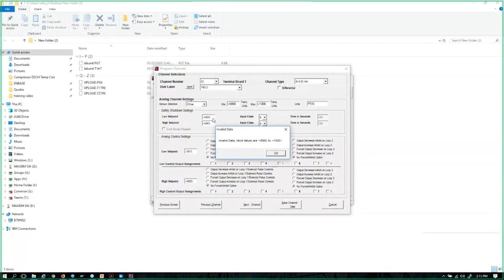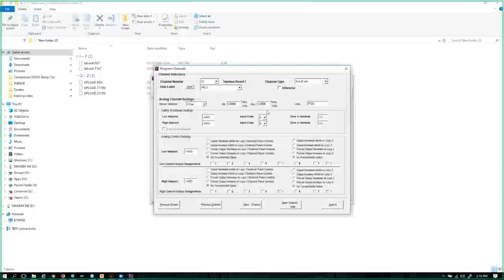And it's telling me my values are invalid. That's kind of a pesky little message, because usually you say okay twice and it'll change the values over here automatically for you. But now that you've selected the sensor type as other, you scale it manually. So we'll tell it 4 milliamps is what it's wanting to know. What does 4 milliamps equal? I said that we would use a 0 to 2000 as our model here a minute ago, so 4 milliamps is going to equal 0 PSI. Likewise, on the 20 milliamp side, 20 milliamps is going to equal 2000. So you always want to scale a 4 to 20 manually, in this method.